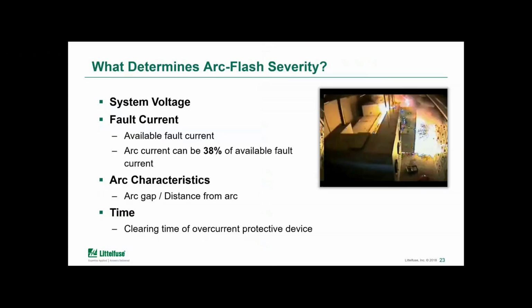Now, if we're looking at arc flash and what we can do about it, first we should look at what determines the severity of the arc flash. Here we're talking about current squared and time, and that current squared times time is the thermal energy from the arc flash. But the actual system energy that's used to run motors, for example, is a function of the system voltage and current. Psychologically, there is a bit of a perception that low voltage might be safer. So an electrician might think they can work live on 480 volts without as much hesitation as they would when moving to a 15 kV system. But really, the nominal current on the 480 volt system would usually be higher. Now, the available fault current is what can determine the amount of energy available to the arc and if there's sufficient energy to maintain that arc.